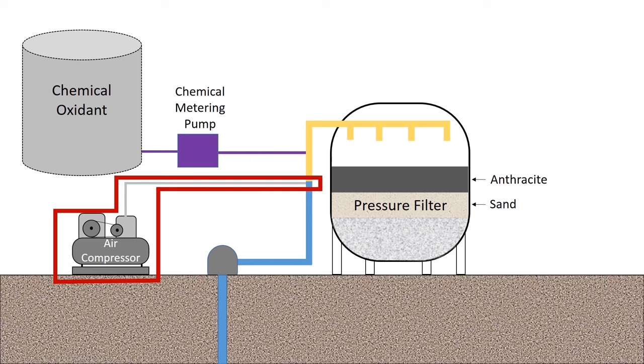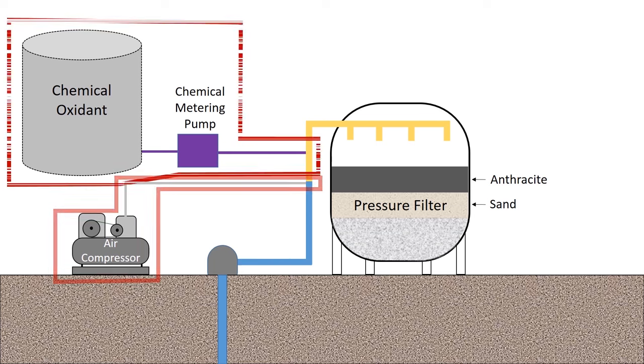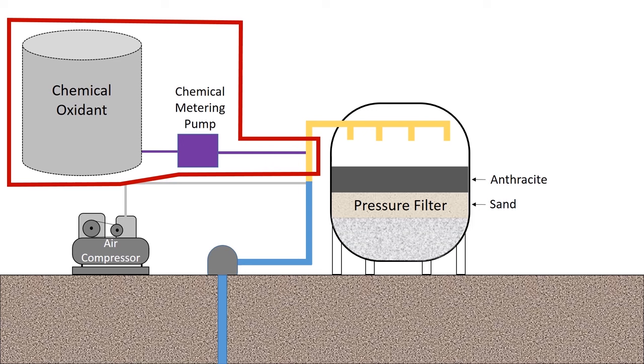Manganese typically requires chemical oxidation. So here we have our chemical oxidant. It could be chlorine, it could be potassium permanganate, it could be ozone, but at any rate, some chemical is used to oxidize the iron and the manganese that's in solution. And here we'll just pretend that it's potassium permanganate, since our feed line and our feed pump is purple.